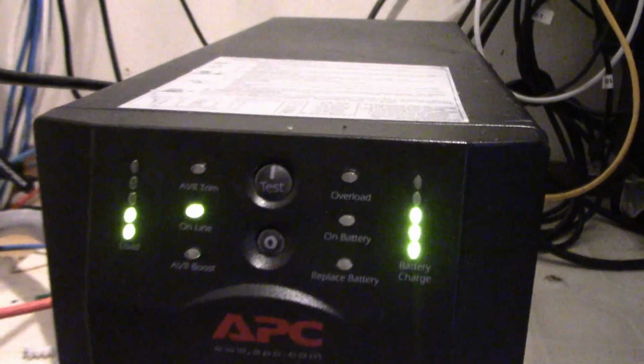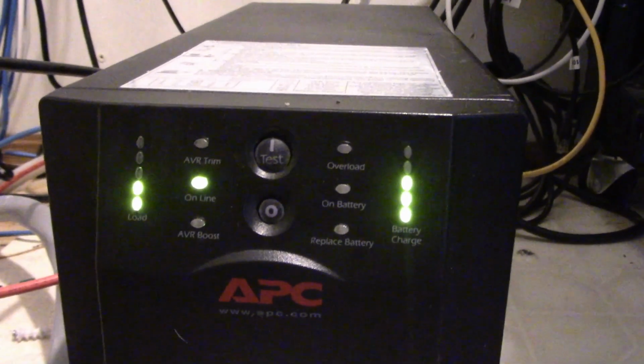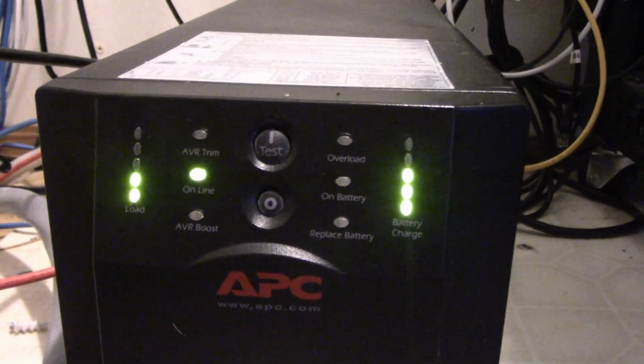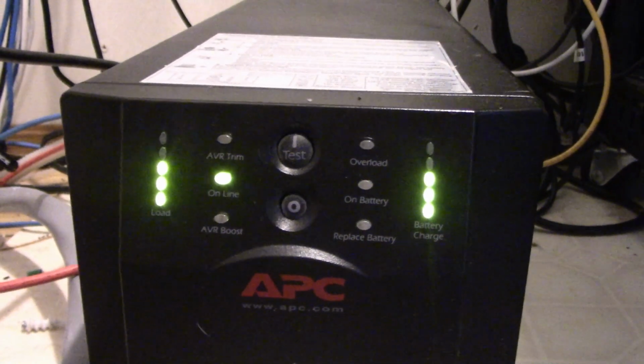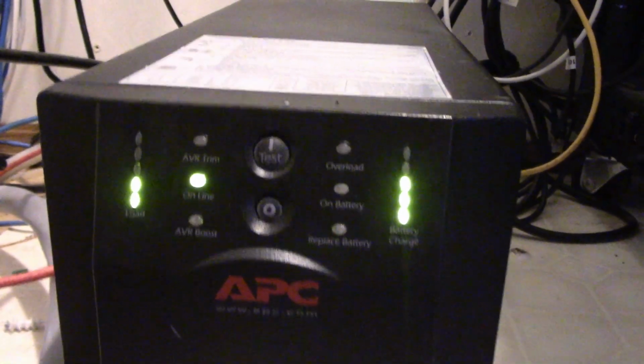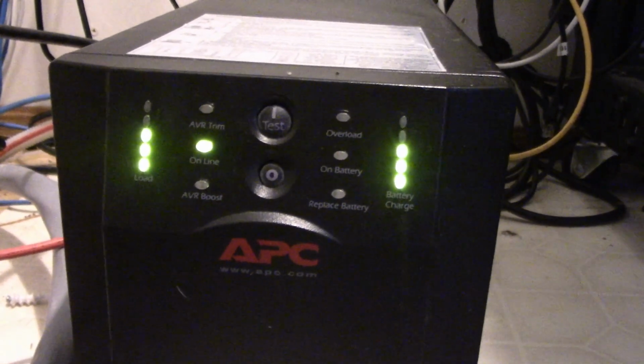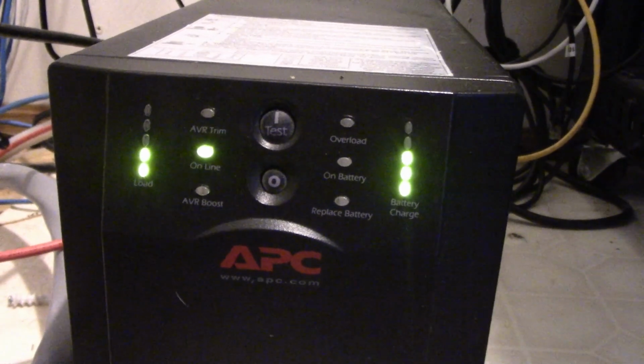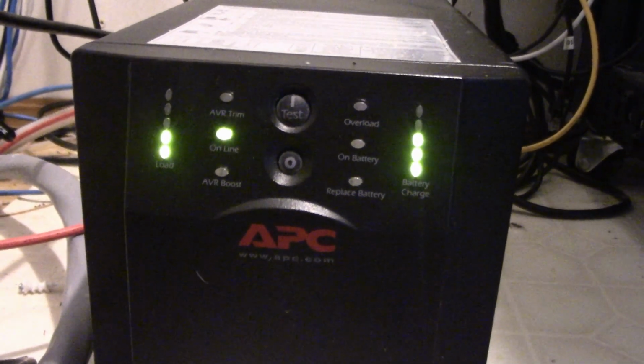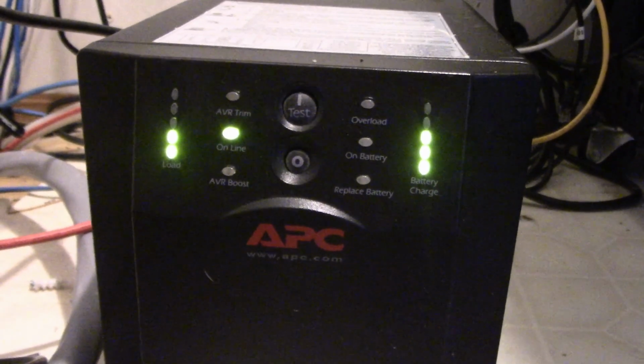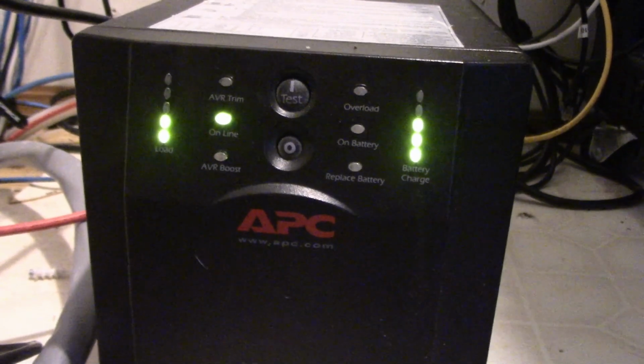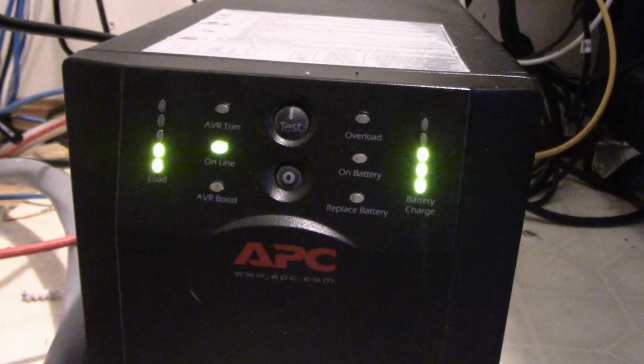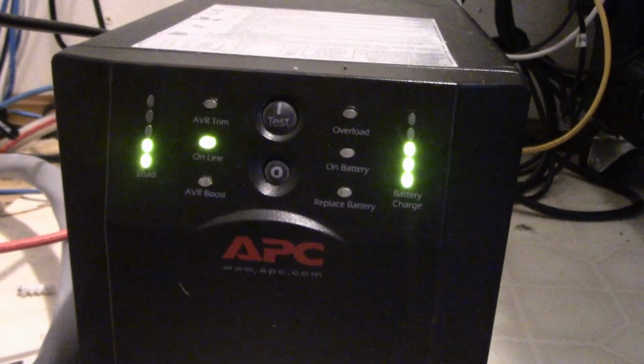So I don't know whether this new battery is a lower capacity or whether it's just not actually fully charged. It was fully charged according to the UPS software, when I ran the calibration test, and I ran it at more than 20% load. It's got about a 35-40% load on it, as you can see.